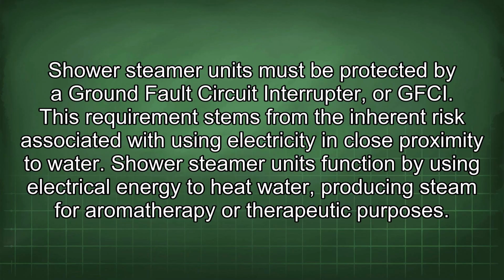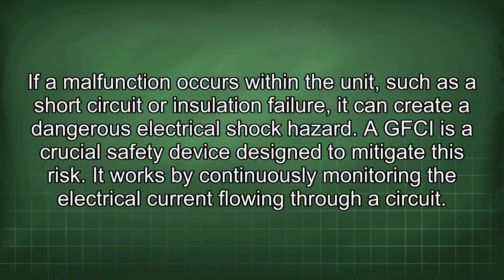Shower steamer units must be protected by a ground fault circuit interrupter, or GFCI. This requirement stems from the inherent risk associated with using electricity in close proximity to water. Shower steamer units function by using electrical energy to heat water, producing steam for aromatherapy or therapeutic purposes. If a malfunction occurs within the unit, such as a short circuit or insulation failure, it can create a dangerous electrical shock hazard. A GFCI is a crucial safety device designed to mitigate this risk.